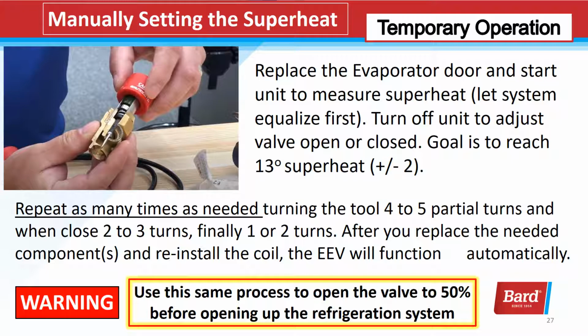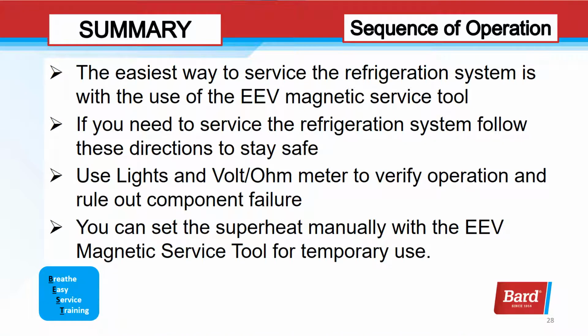And then leave the coil off until you get the part and you're ready to put the EEV system back in service. After you replace the needed components and reinstall the coil, the valve will work automatically. It will just move to the right position. Use this same process to open the valve to 50% before opening up the refrigeration system. In summary, the easiest way to service the refrigeration system is with the use of the EEV magnetic service tool. If you need to service the refrigeration system, follow these directions to stay safe.